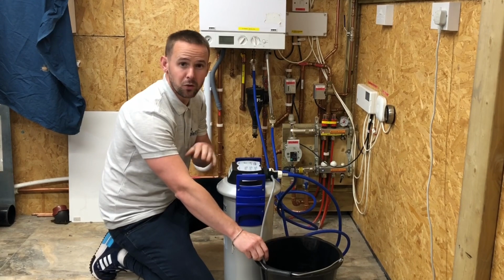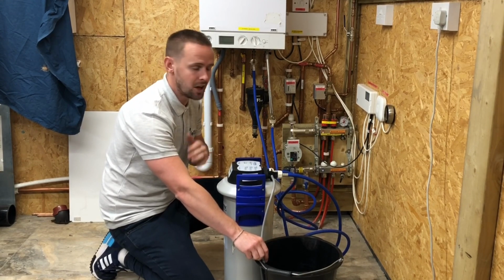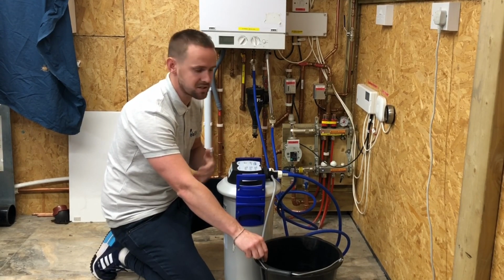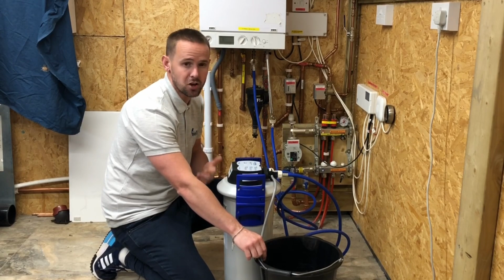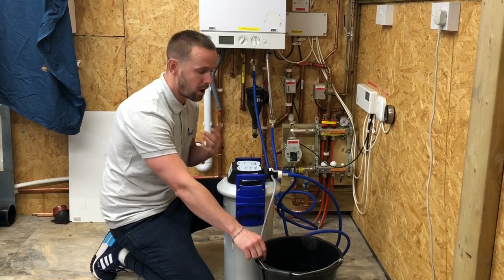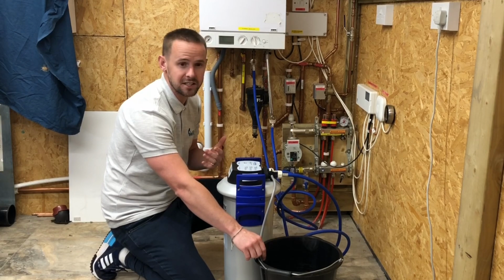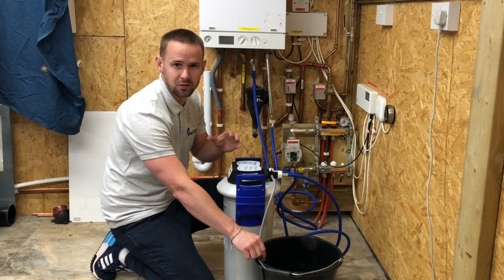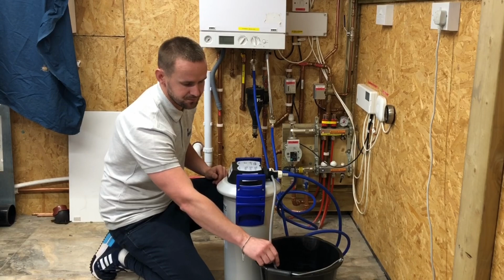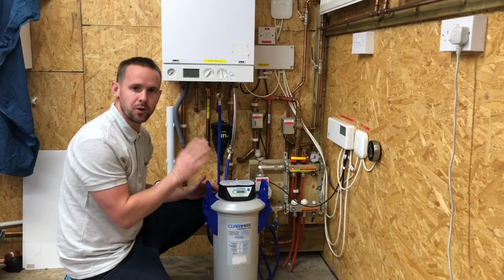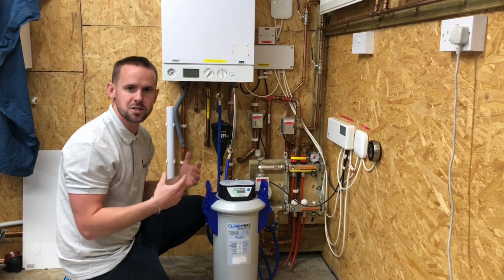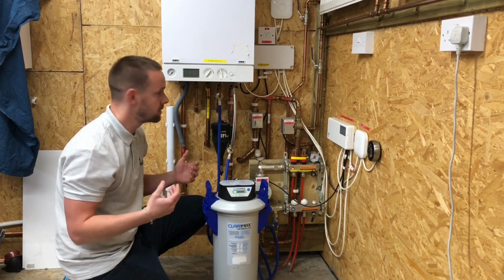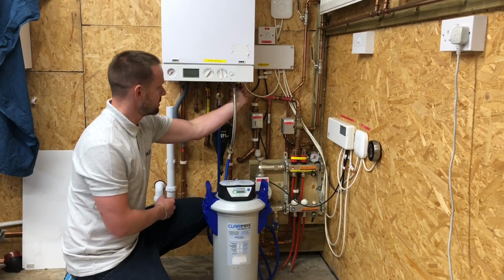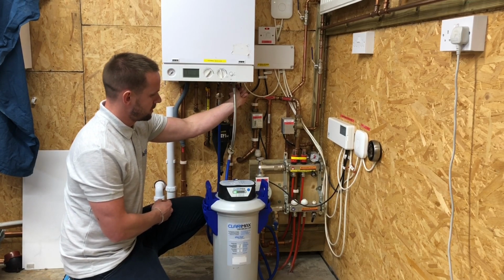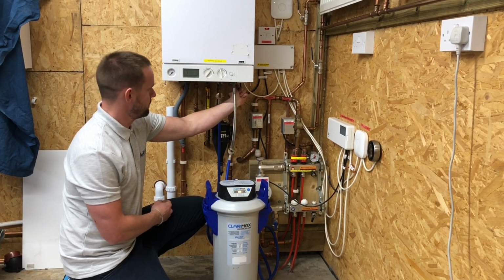What we're going to do, we're going to fill the bucket up once, and that'll be fine. You don't have to do this every time you use the device. It's the first time you use the cartridge, you have to do it. My advice would be, every time you reconnect it, just a little bit, make sure we've got no air within there. So once the cartridge is bled, we're ready to fill the system. So you just fill the system like you would any normal system. So I'm just going to open up the other side of the filling loop here. Here the water starts going in the system.